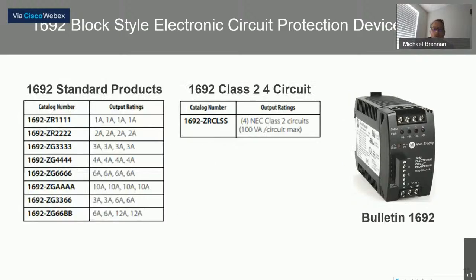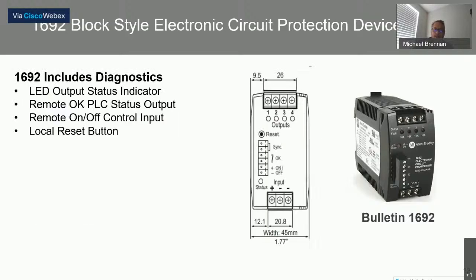Now, here's an example of the different numbers that are available and the different current ratings or output ratings that are available. You'll see that they're available up to 12 amps with outputs, but additionally, there is one Class 2 part number that gives you 100 VA max per circuit, a Class 2 specific device. So again, like we discussed, there's LED annunciation, there's an OK input diagnostic that can go back to the PLC. And additionally, what I might not have discussed is that you can even control the outputs directly from the PLC.